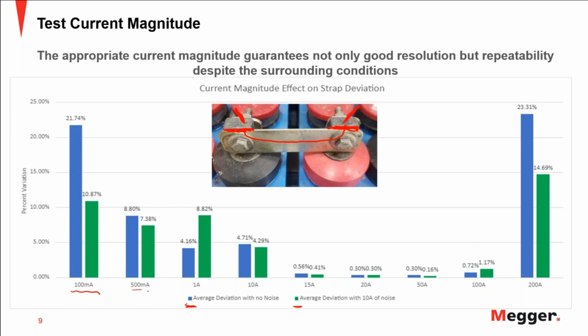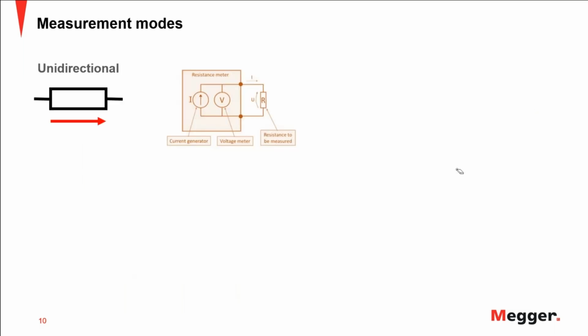And as we increase the current, you can see that the error or the deviation reduces. And well, it's a strap application, so it's a battery application, not a bonding application. So you can see that the higher the current, the more accurate the results, with less deviation. And when we injected a current of 200 amps, now the result also has a big deviation between the different tests, because now the temperature of the sample or this connection changed. So you can see here basically all the benefit of testing with the right current and using the right magnitude.